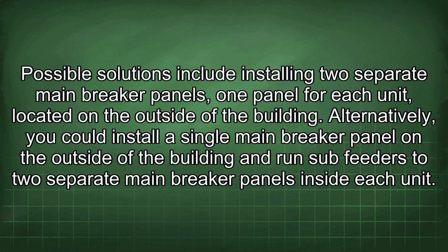Possible solutions include installing 2 separate main breaker panels, 1 panel for each unit, located on the outside of the building. Alternatively, you could install a single main breaker panel on the outside of the building and run sub-feeders to 2 separate main breaker panels inside each unit.